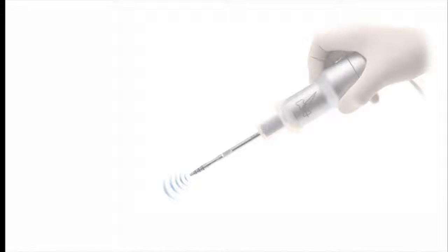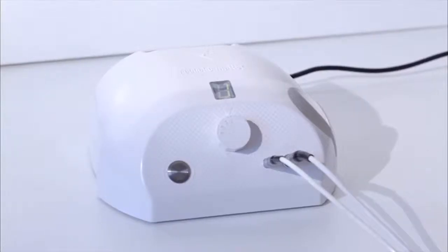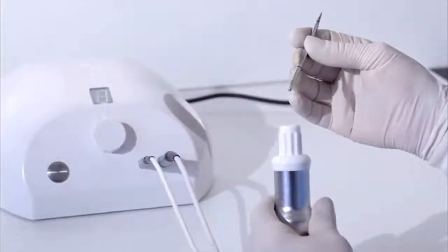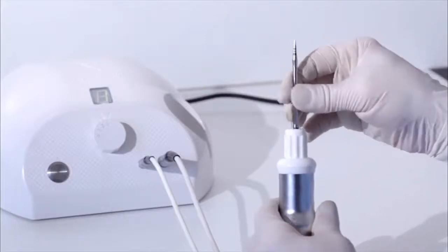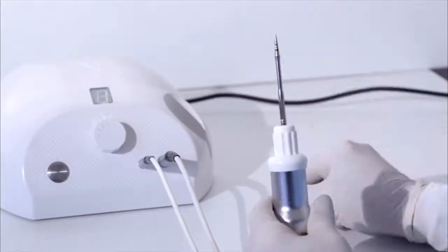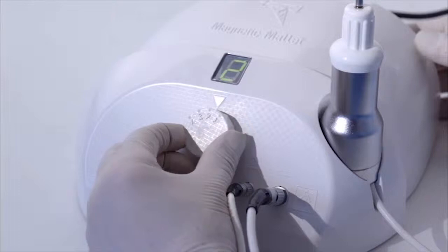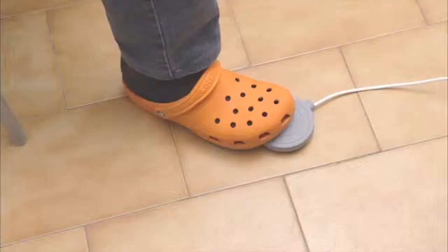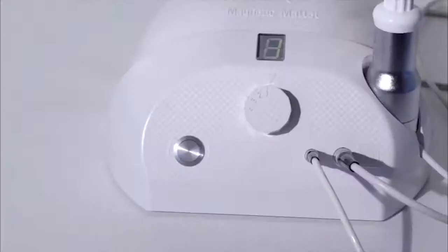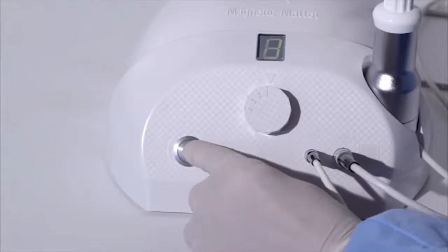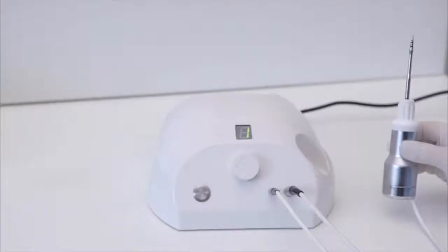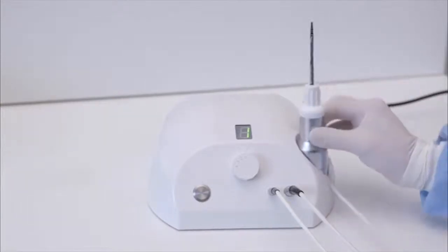MetaErgonomica designed a magnetic, dynamical handpiece powered by a control unit, delivering preset forces by timing of applications. The osteotome is firmly hooked up in the instrument, and the application time of the force is the best one to achieve the desired plastic deformation. The device is designed to apply four forces of different strengths, and the handpiece is operated through its ergonomic foot switch. If needed, it can also be operated by the manual button placed on the power supply. The handpiece can be easily placed in its housing during the various steps of the surgery.